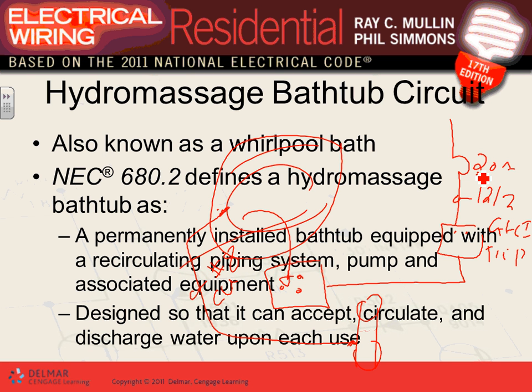I don't know. We don't size for it. I believe it's part of it. We do not provide an overload for hydromassage bathtub, from what I've seen. If the overload is not provided with the bathtub, which I don't think they provided with this, then this breaker acts in two duties: short circuit ground fault and overload protection. That's acceptable. So I think for hydromassage bathtub, the 20 amp circuit breaker will act as your overload as well as your short circuit ground fault.